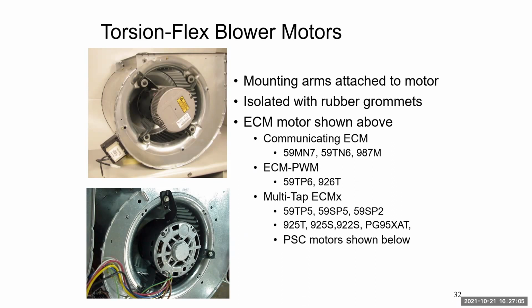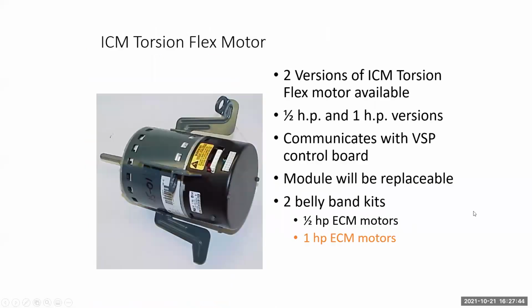With that being said, check your motor. To do that, ohm out between, on your motor side of that Molex plug, 1 and 2, 1 and 3, and 2 and 3. They should all be equal, not to exceed 20. If you're under 20 and they're all equal, spin that motor. It should spin freely. I state spinning your motor with your module disconnected because your module will actually create a magnetic force that will hold that motor from spinning 100% freely. So with the module disconnected, it should spin free. If all that's said and done, your motor's 99% of the time good. It's in your module. Moving on.